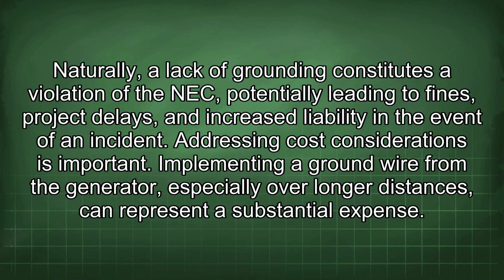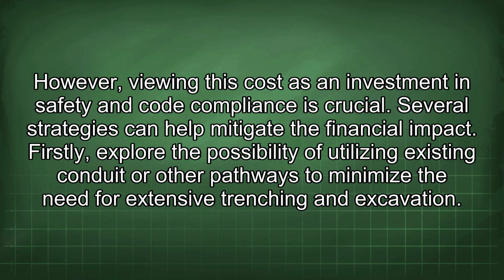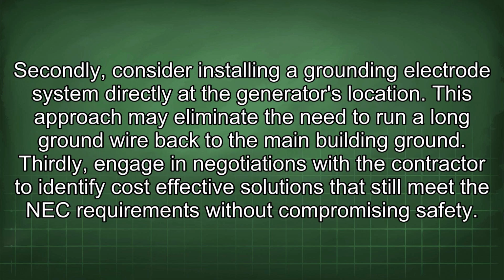Addressing cost considerations is important. Implementing a ground wire from the generator, especially over longer distances, can represent a substantial expense. However, viewing this cost as an investment in safety and code compliance is crucial. Several strategies can help mitigate the financial impact. Firstly, explore the possibility of utilizing existing conduit or other pathways to minimize the need for extensive trenching and excavation. Secondly, consider installing a grounding electrode system directly at the generator's location. This approach may eliminate the need to run a long ground wire back to the main building ground. Thirdly, engage in negotiations with the contractor to identify cost-effective solutions that still meet the NEC requirements without compromising safety.